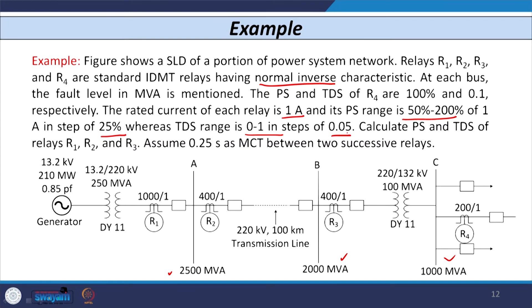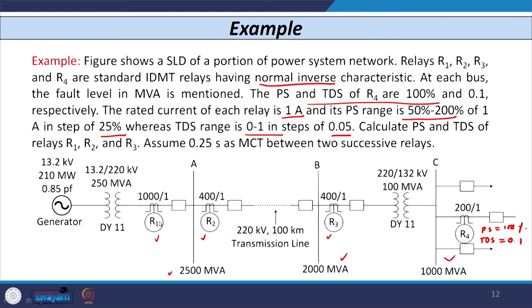The plug setting and time dial setting of relay R4 are given: plug setting of R4 is 100 percent of 1 ampere (the relay rated current), and its TDS value is 0.1. We need to calculate the plug setting and time dial setting of all other three relays — R3, R2, and R1. We will solve this example considering that R1, R2, R3, R4 are phase relays.